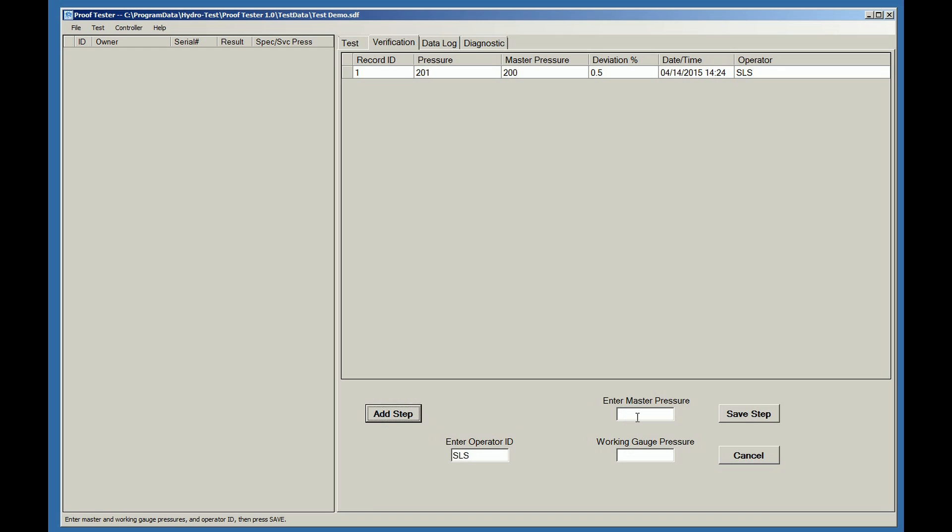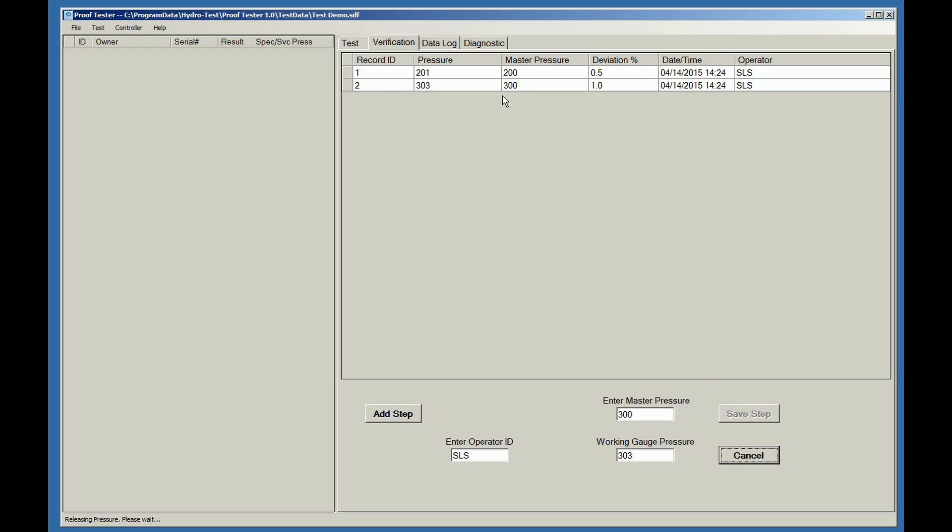To perform additional verification pressure points, always click on the Add Step button and simply type in the pressures and click on the Save Step button. For each step, the data is calculated, the deviation is shown along with the date and time stamp and the operator's initials.